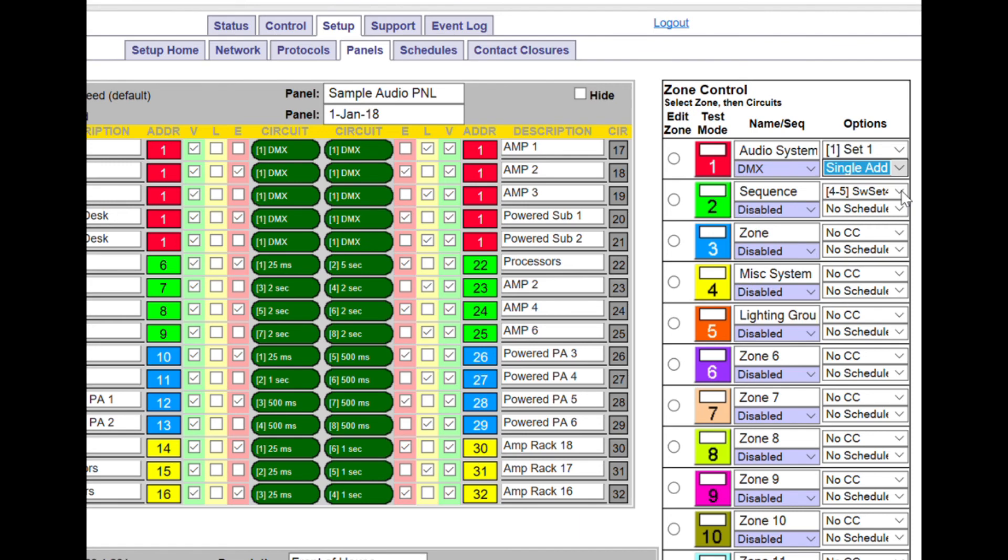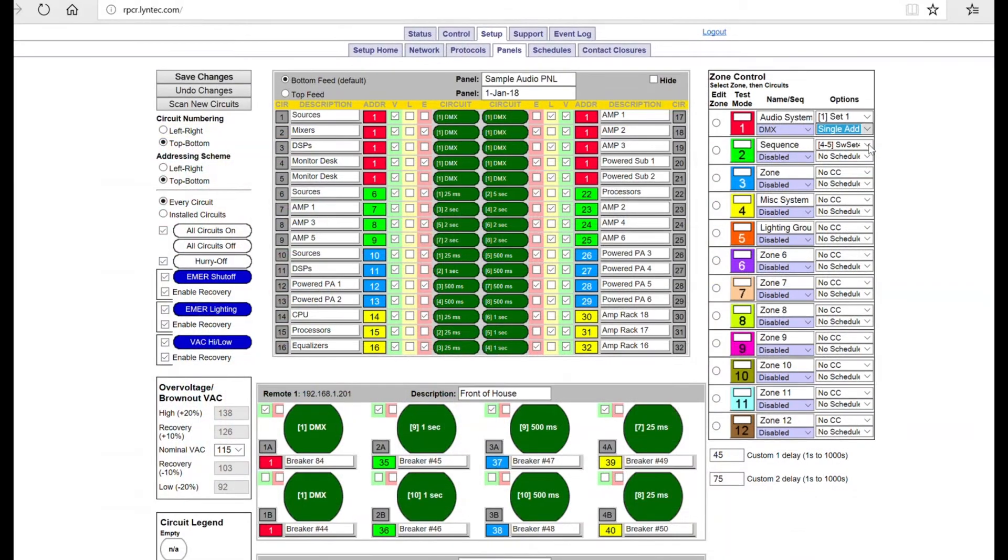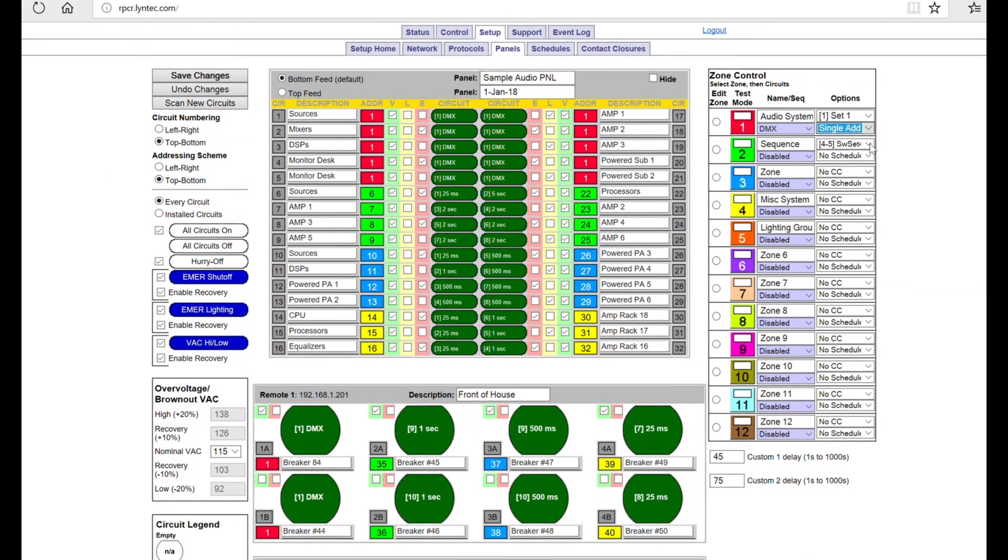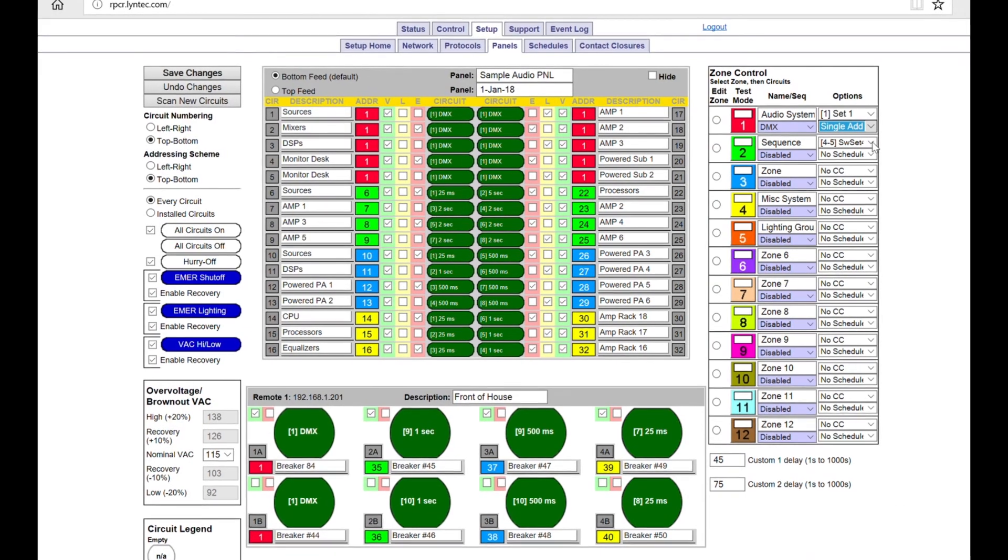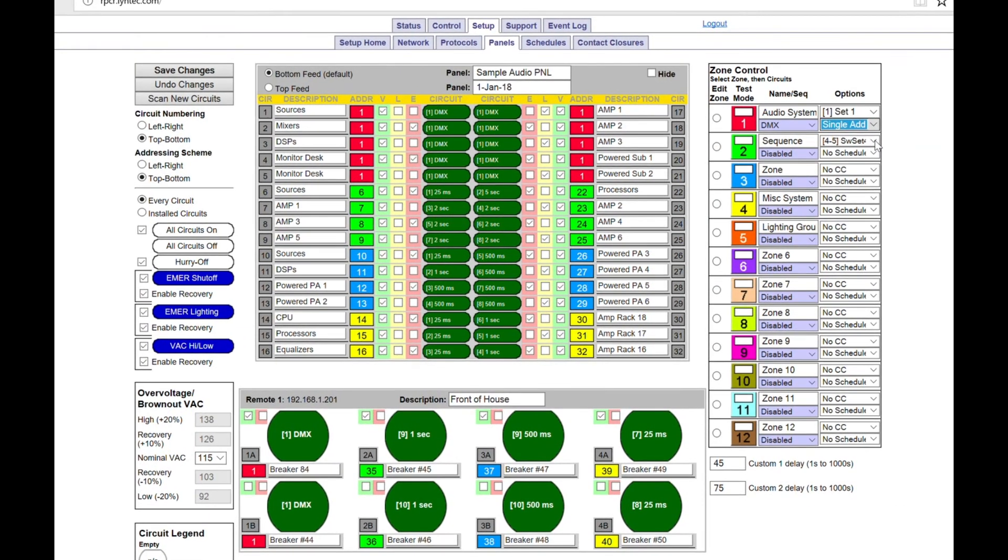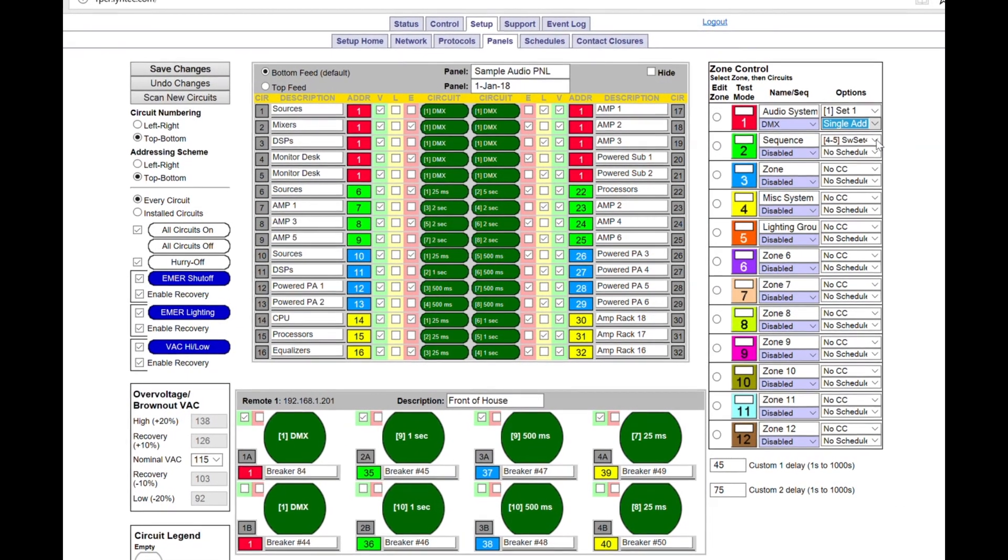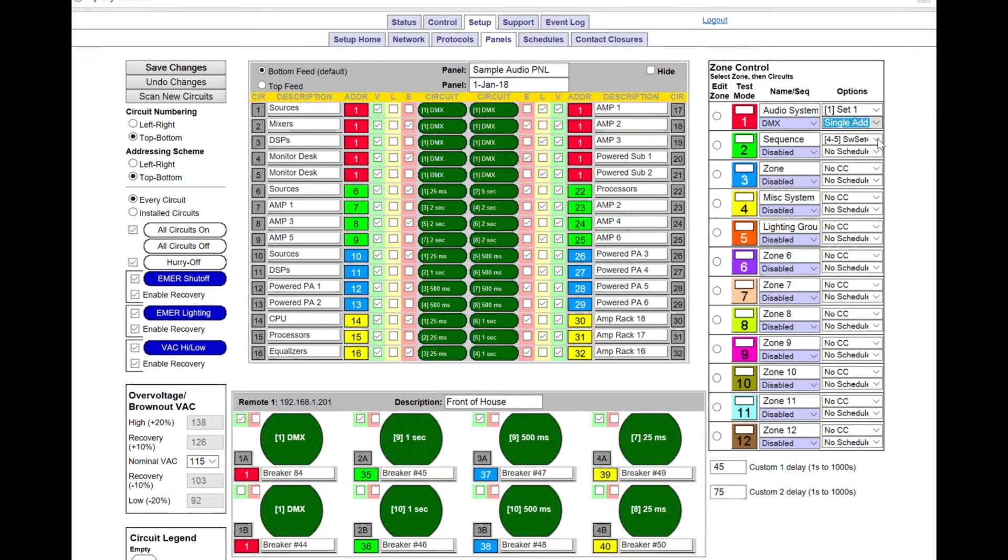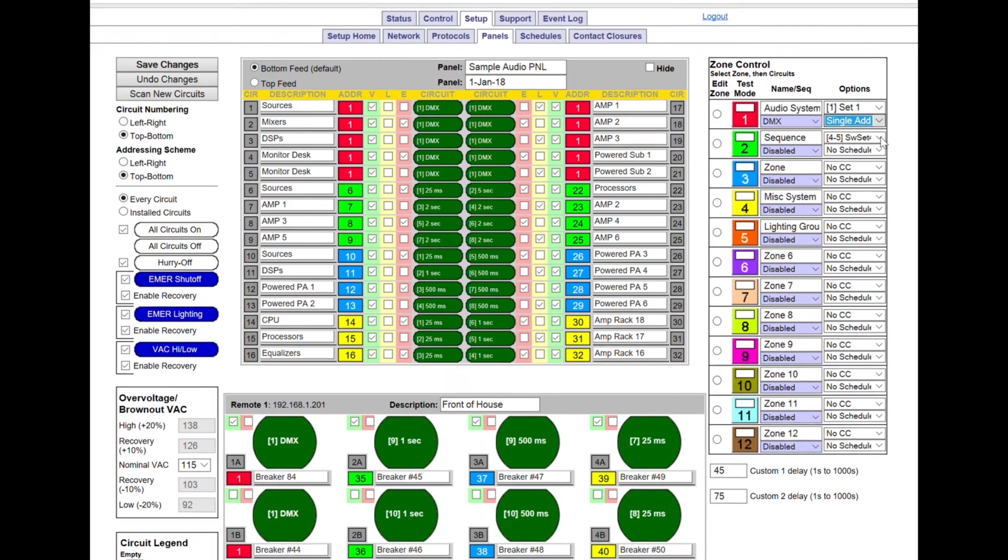Next, select Single Address from the drop-down menu under the Options column. Note that the default is Individual Address. The addresses of all the circuits in Zone 1 are now set to the starting address selected on the Panels Protocol page. In this case, that is DMX Channel 1.